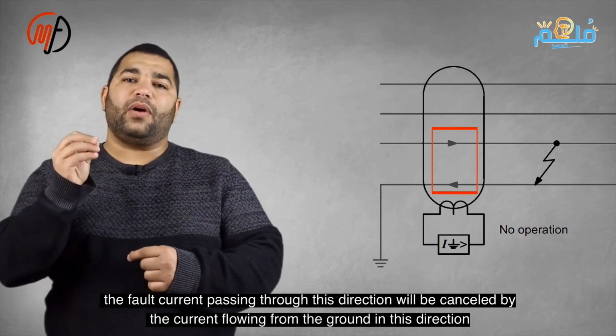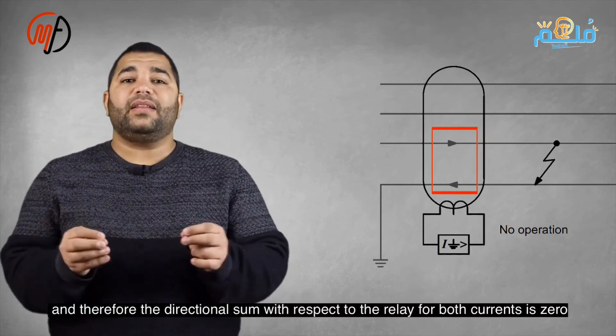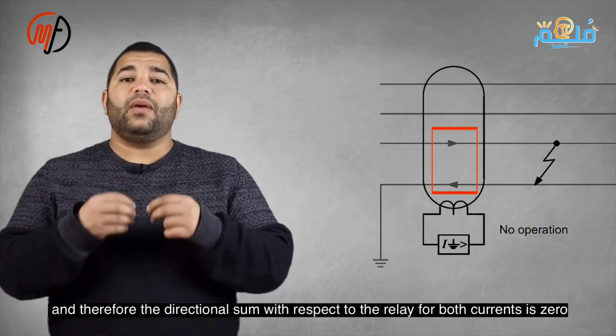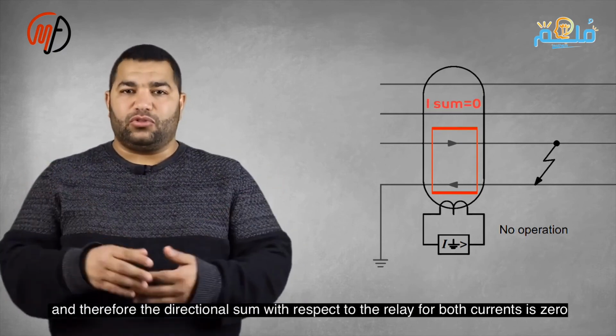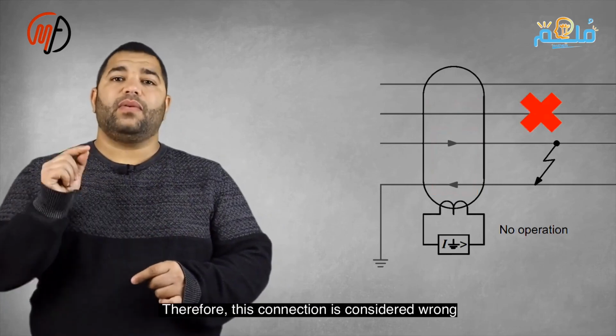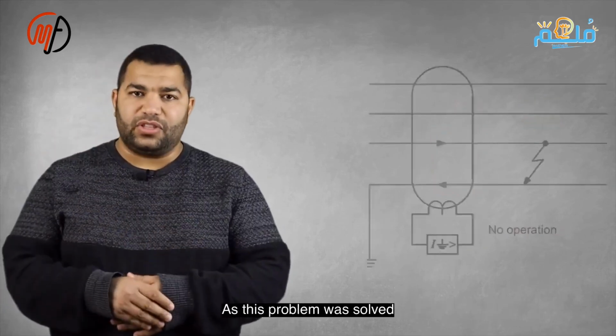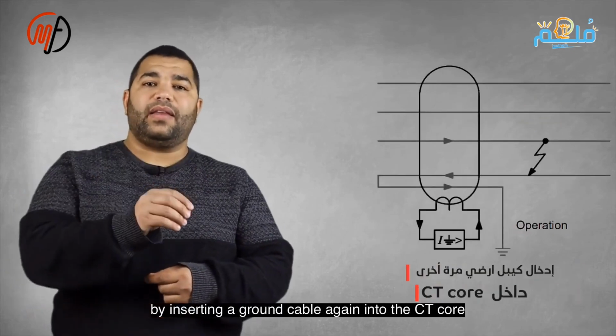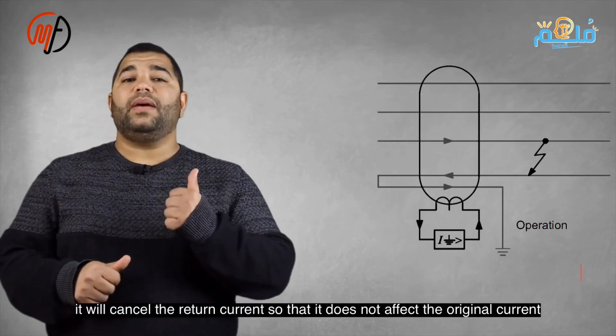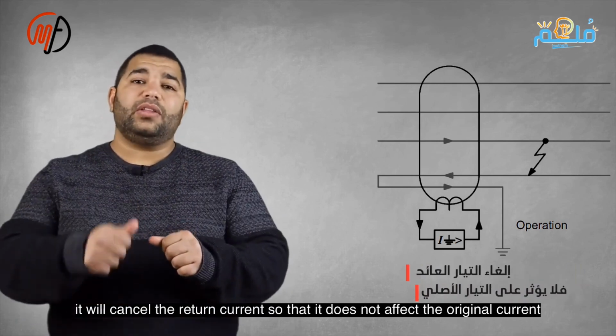The return current from the ground will neutralize the original current, thus this connection is incorrect. Reintroducing a grounding cable into the CT core neutralizes the return current, preserving the original current. This enables the relay to detect imbalance and trip the breaker. Restoring the sheath earth connection to the CT core is crucial.